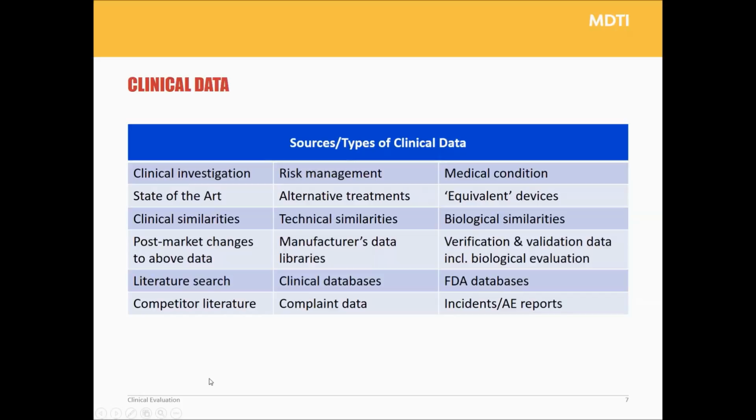They're still inviting manufacturers to use equivalence rather than pre-market clinical investigation, but it's very, very tight, and the new MedDev insists that that must be one single predicate or equivalent device rather than previously it was possible to mix and match from other devices. So that's a big difference, which means that manufacturers are more likely to have to do pre-market investigations.